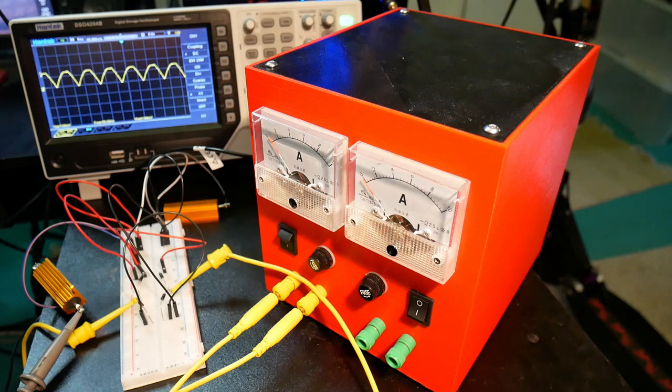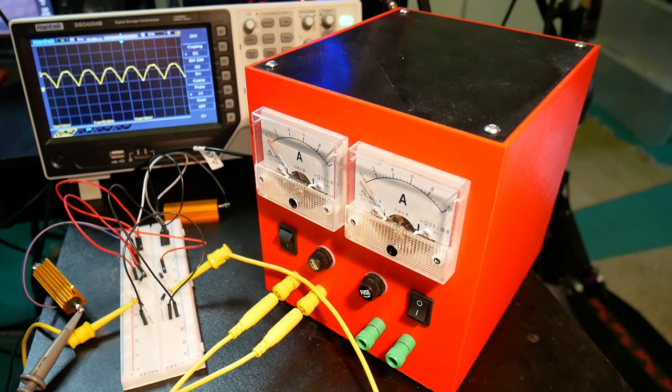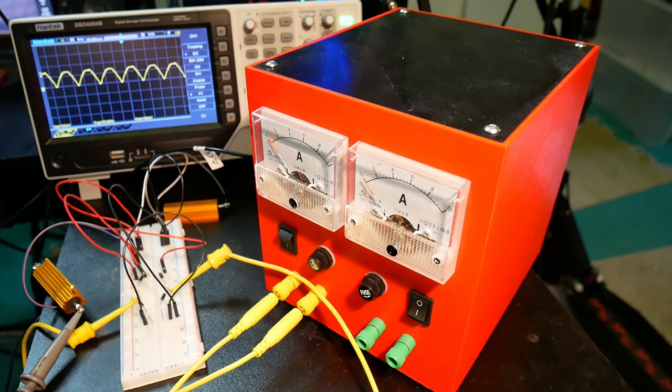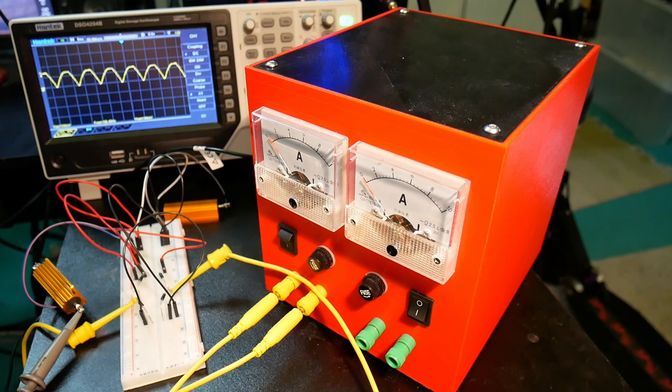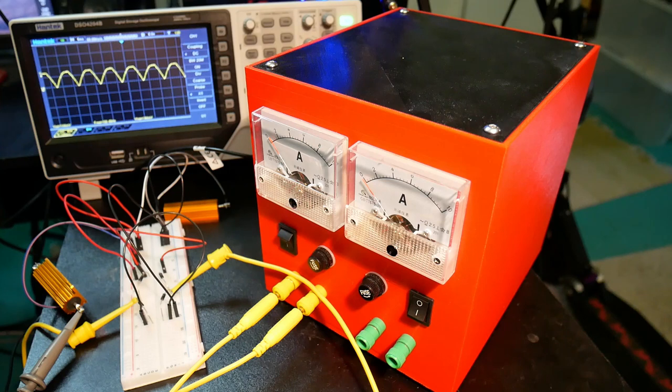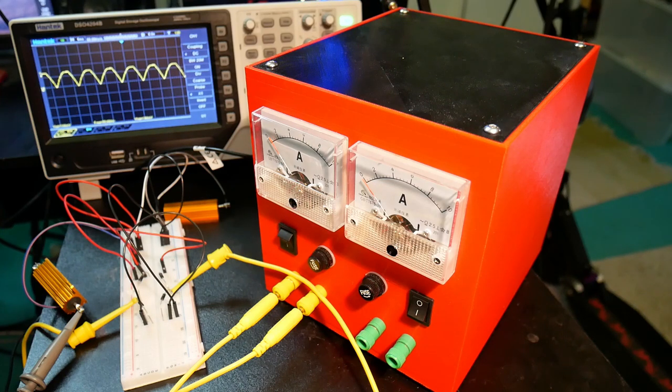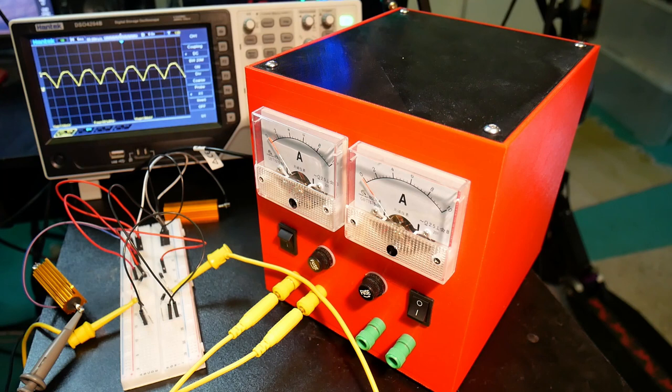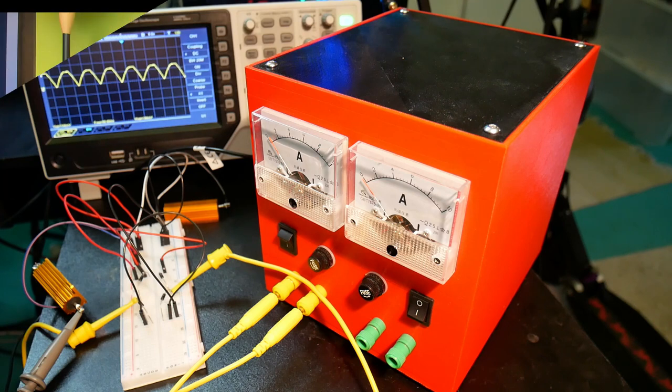But if you start adding capacitors, with the first one, and then you throw in even more, it increases the current, the peak current. And the peak current will go, in this case, with the first capacitor, it'll jump to two and a half amps. So you can see that that will increase the thermal load of the transformer.